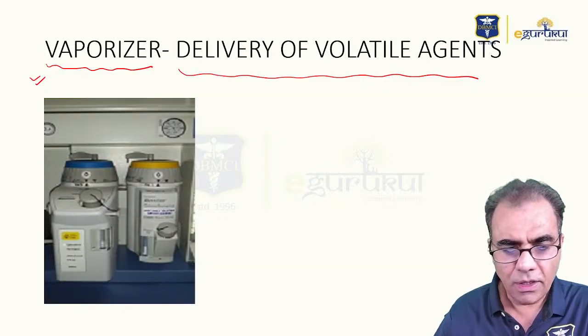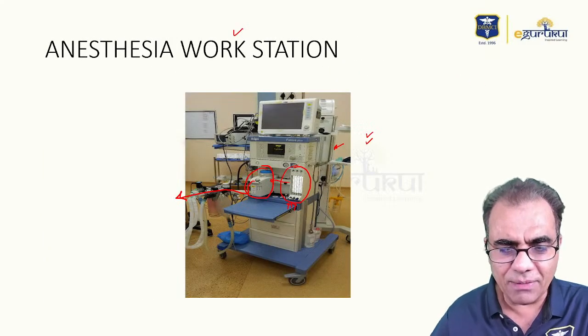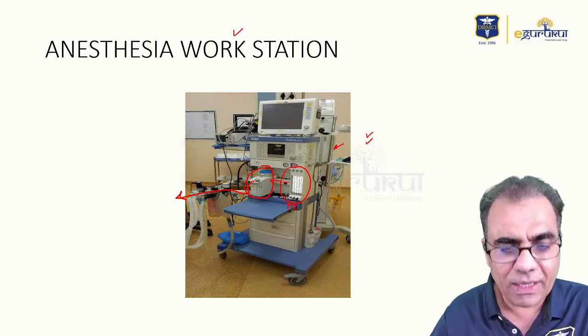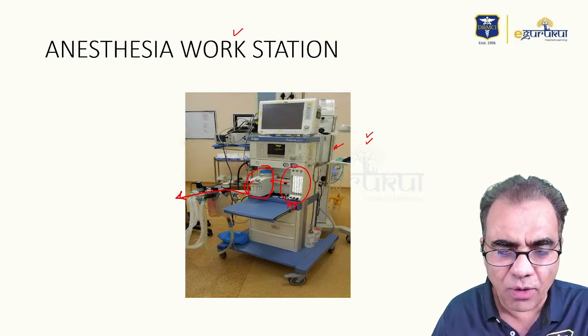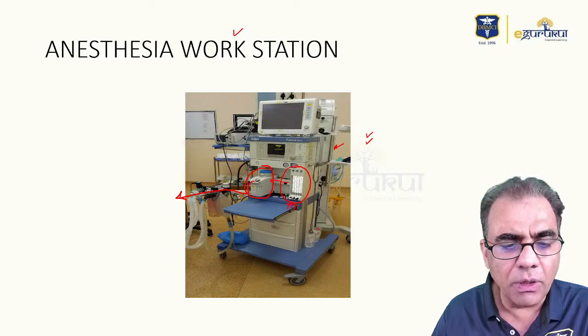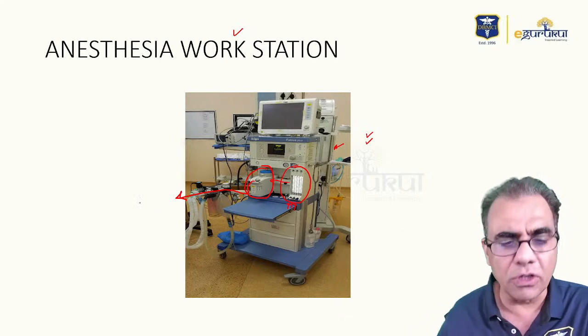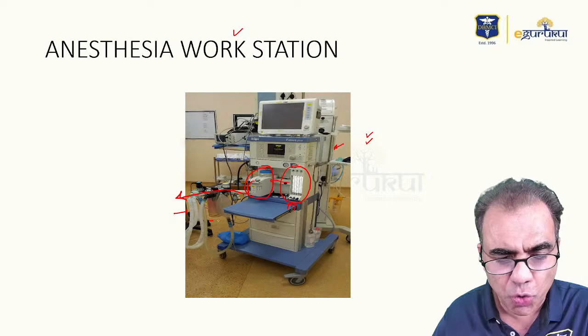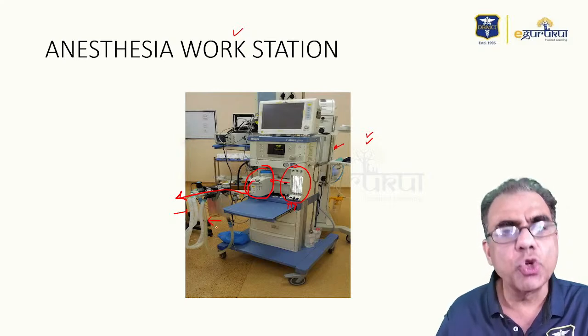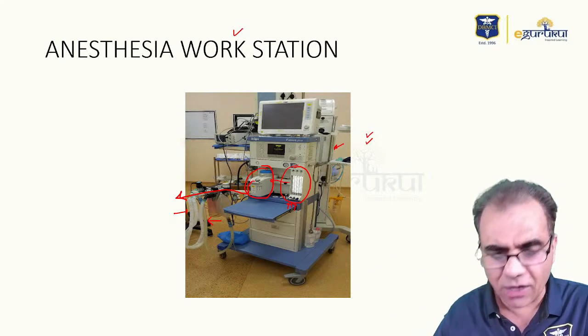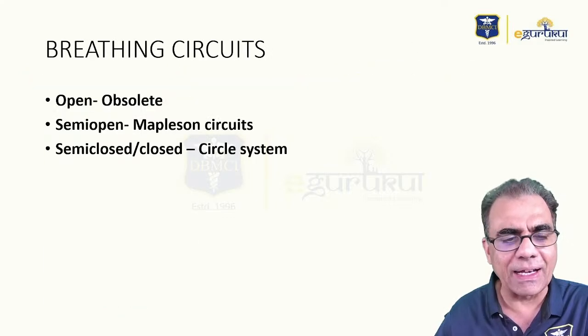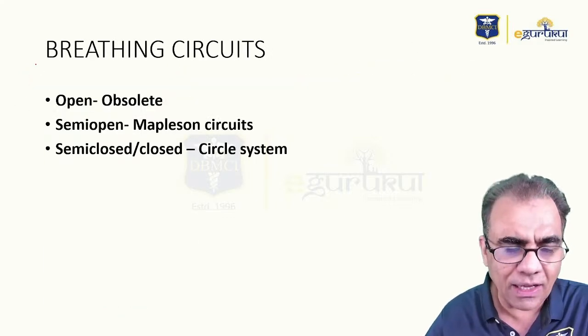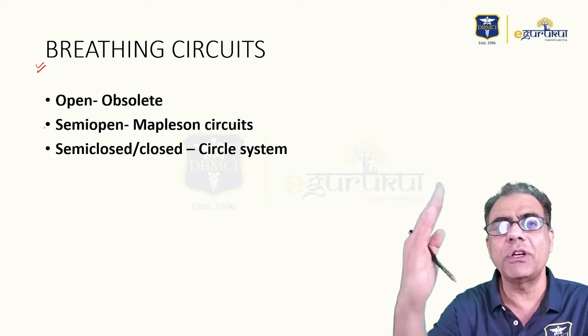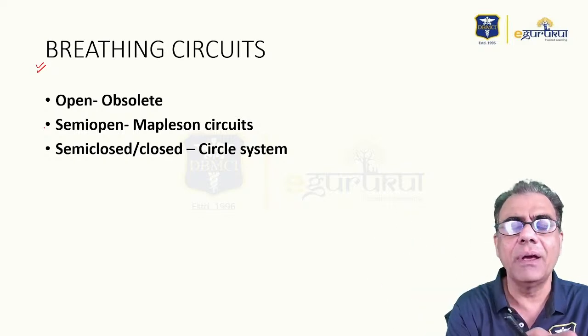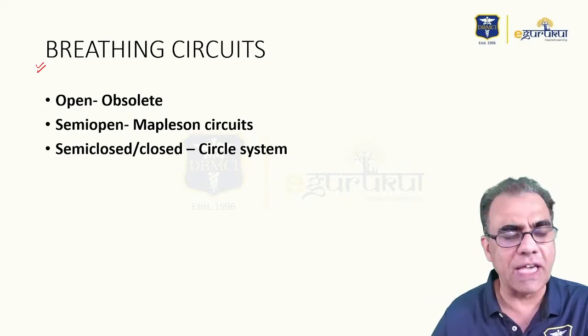Now, gases are delivered at the machine outlet, but these need to be delivered from the machine outlet to the patient. For that, you need these tubings. These tubings are called breathing circuits. So breathing circuits are nothing but the connection between the anesthesia machine and the patient for the delivery of these gases.